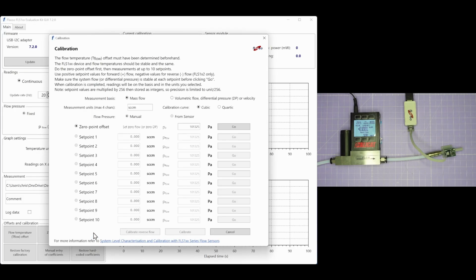Using the calibration window in the GUI, we're going to choose our measurement basis. I'm going to be measuring mass flow, and our measurement units. In my case, I'm going to be measuring in SLPM. Using a cubic calibration curve, this is going to be typical for most standard range applications, and our flow pressure is going to be set manually at 101.3 kPa. Now we go through the set points, and I'm going to be using 3 set points at 10, 50 and 90% of my measurement range, which in this case is going to be 0.3, 1.5 and 2.7 litres a minute.